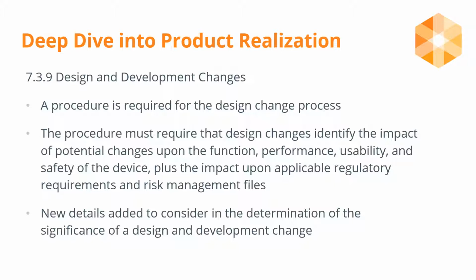A standard operating procedure defining the design change process is required and must require identification of impact of potential changes on device, function, performance, usability, and safety, and also the impact on applicable regulatory requirements and risk management files. New details have been added for consideration in determining significance of a design and development change.